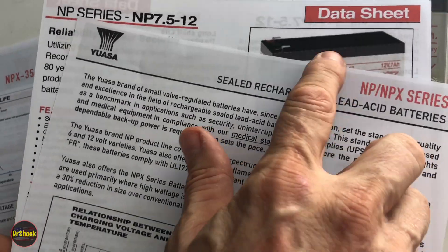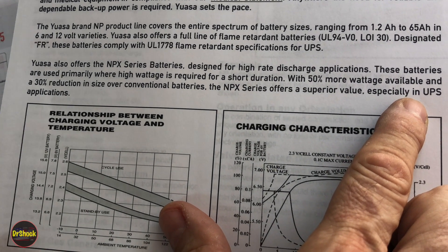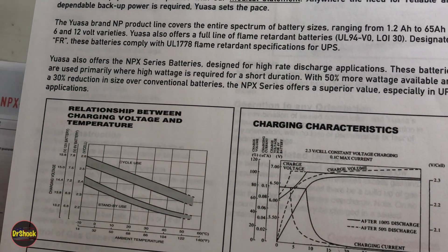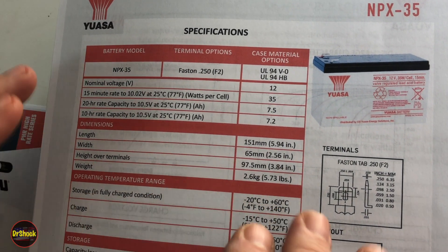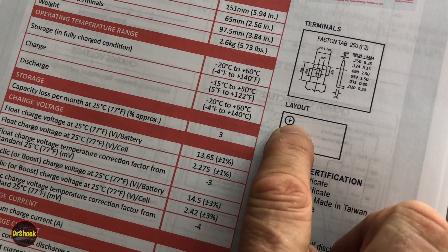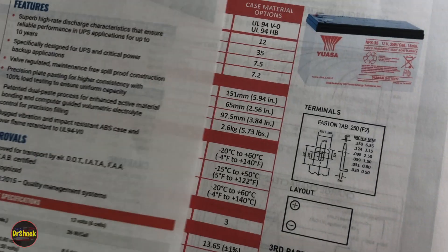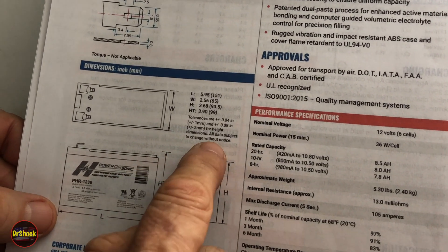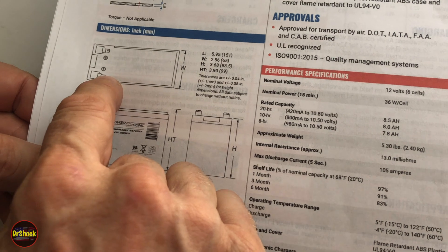A better upgrade would be the Yuasa NPX series, specifically designed for UPS applications. The NPX35 meets all the dimensional specifications, has negative-left positive-right layout, and F2 spade terminals — that'll work fine. Another battery I'd recommend — and the one I'm actually using because the NPX35 was out of stock — is the Power Sonic PHR-1236. Again, confirm the height, width, length, negative on the left, positive on the right, and F2-type terminals. Those are the two batteries I'd recommend.